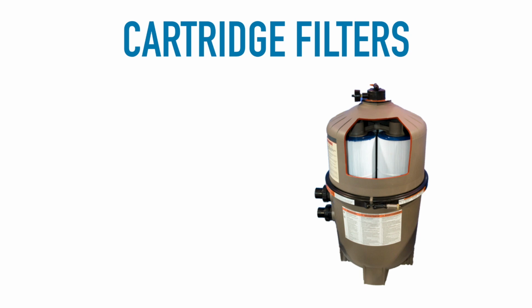Now, cartridge filters. Cartridge filters are going to be our next filter on the list. They've got a filter media rate of 0.375 gallons per minute per square foot. This water is eking out of these cartridges at every square foot. So imagine if I had a pool that needed to run at 92 gallons per minute and I was running at 0.375 gallons per minute per square foot. These filters need to be gigantic to make up for that when it comes to the square footage.